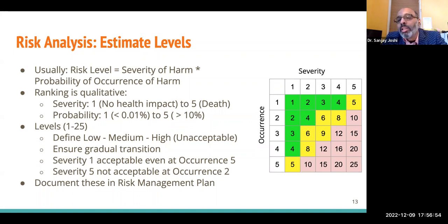If your product is the integration product from all the devices, you don't worry about what could go wrong with each of the 3 or 4 devices. What you need to worry about is what could go wrong when they send their data to you. That either they send the wrong data, they send corrupted data, or they don't send data. And how are you going to handle that interaction? Are you going to show the status of connectivity? Are you going to show a correct message to the user: hey, I have not received more recent data from this device? Or are you going to show some kind of alarm?